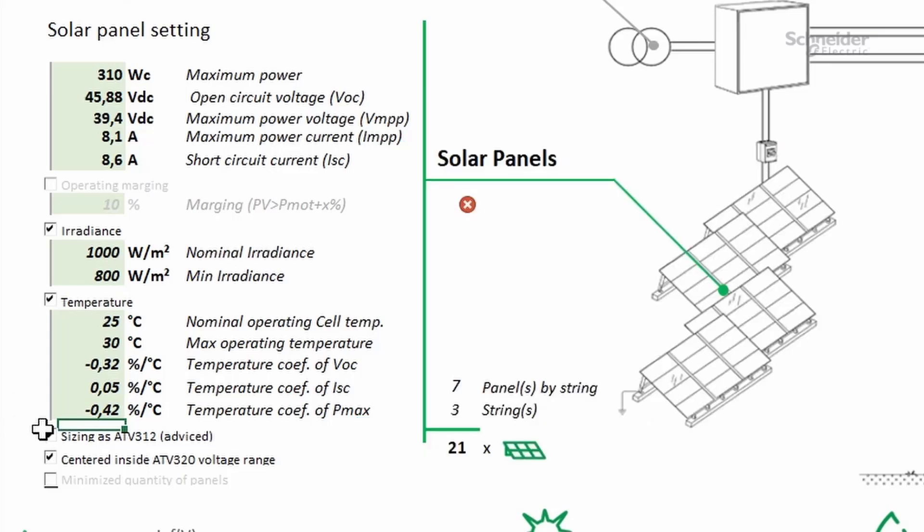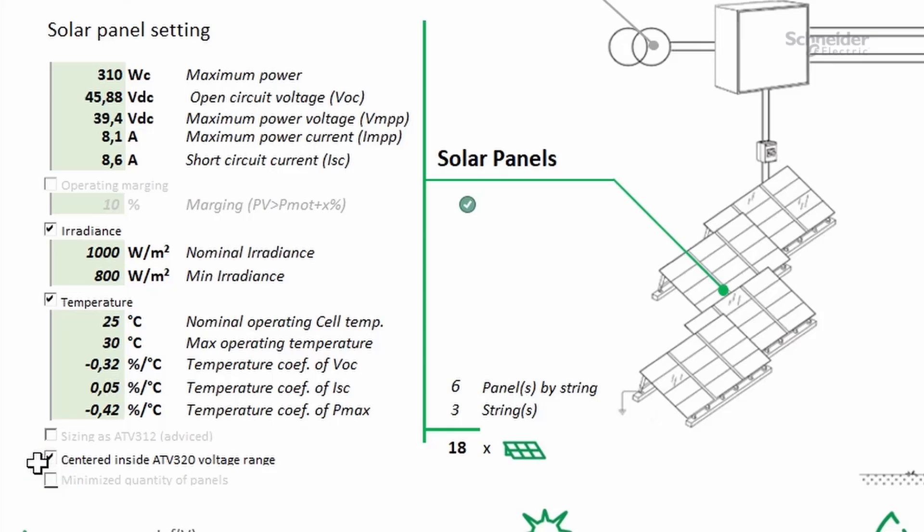In case of substitution, select sizing as ATV312. It will deactivate the low voltage assign parameter. To reduce the probability of triggering an under voltage error trip threshold, or a trip threshold for over voltage error, select centered inside ATV320 voltage range.